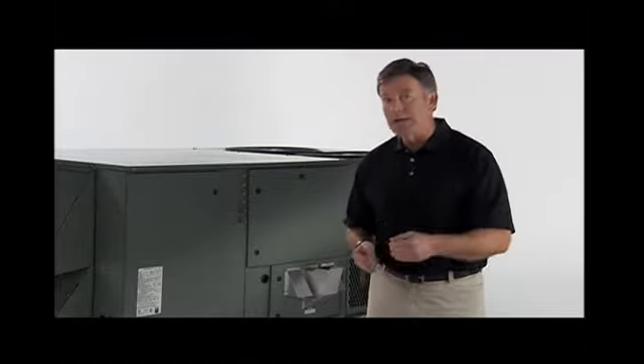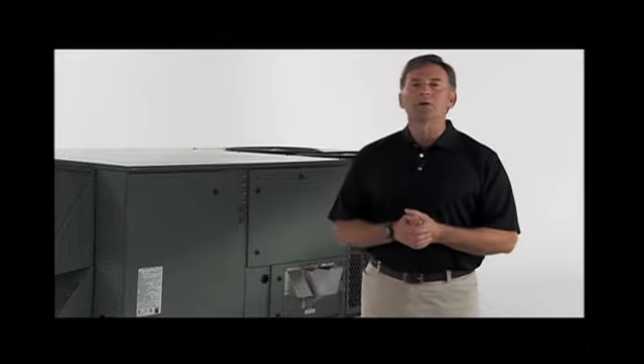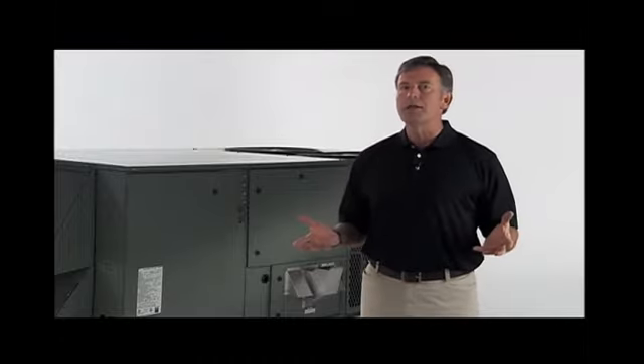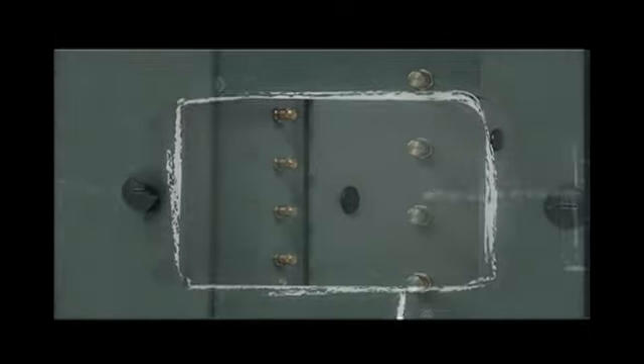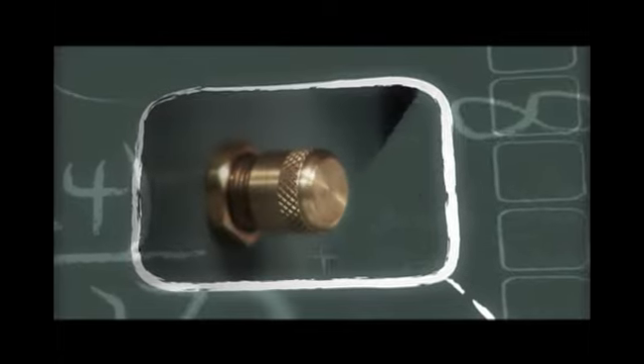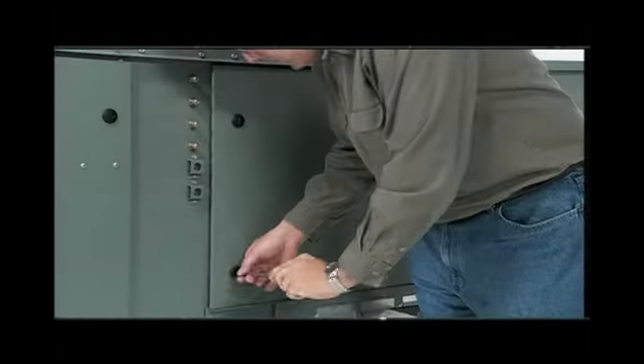Low and high voltage can enter either from the side or through the base. The high voltage connection is terminated at the number 1 compressor contactor. The suggested mounting for the field-installed disconnect is on the exterior side of the electrical control box. Low voltage connections are made through the low voltage terminal strip. For ease of access, the UL required low voltage barrier can be temporarily removed for low voltage termination and then reinstalled.